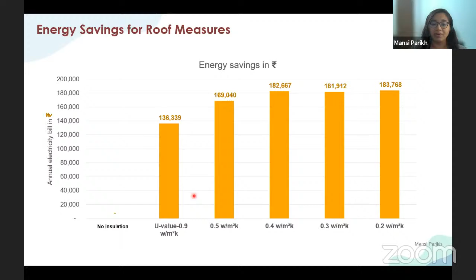That is nothing but incremental cost: the cost of labor and material to incorporate a particular ECM minus the cost of reduction in system sizing. So how do we calculate incremental cost? For the roof ECM, for a particular building, I calculated the roof area required and, based on that, calculated the insulation thickness. Based on the insulation thickness, I came up with the cost for insulation meeting 0.9, 0.4, 0.3 and 0.2 U values. I also did a little market survey to understand the cost implication of applying that insulation. So the incremental cost also includes the labor cost.